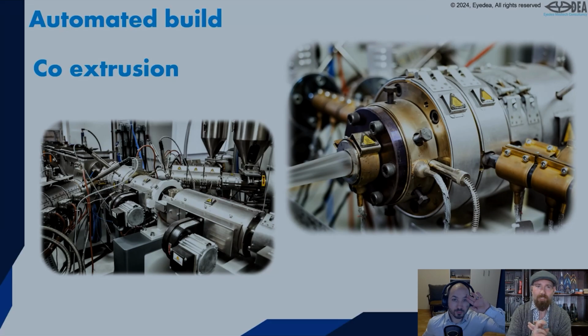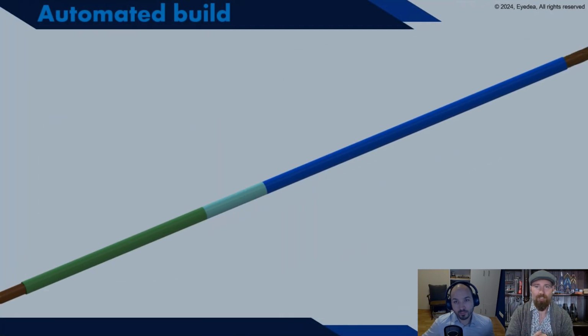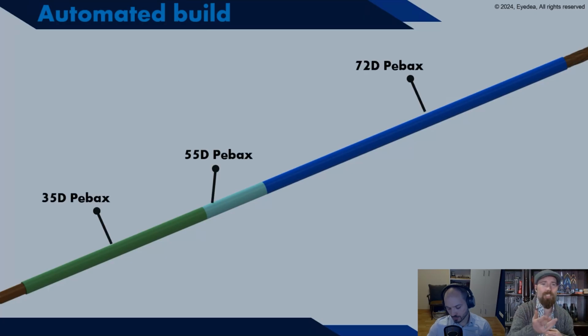And then you could co-extrude onto the outside, but you could do something like dynamic co-extrusion. So there are companies like GMAC who create dynamic co-extruders. So this is if you want to put multiple different jackets onto the same device, and there'll actually be a flow transition between each one of these. And this is the alternative to having to place on each individual jacket. This machine actually just gates on and off different extruders to be able to make those variable durometers. So you could have 72D, 55D, and 35D. That 72 number, 55, that's how hard the material is. So the lower the number, the softer it is. Just for a little bit of reference.